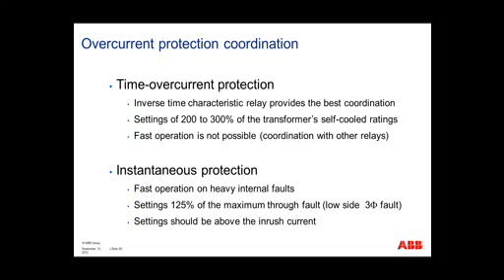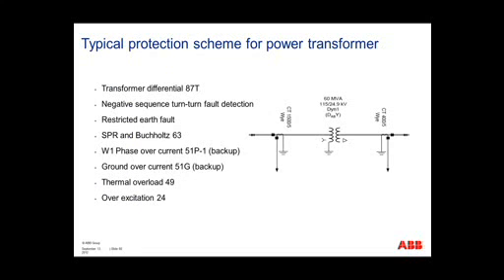Instantaneous protection needs fast operation on heavy internal faults. These are typically your overcurrent protection settings, at 125% of the maximum through fault, and the worst case scenario would be a low side three-phase fault. And of course, you need to consider the inrush current, and the settings should be above that to prevent misoperations.